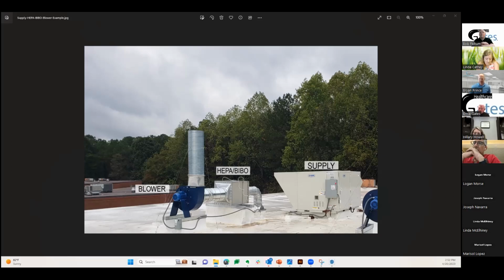Hot gas bypass solenoid valve is only a band-aid, and the point of having a hot gas bypass is to keep the coils from freezing up. That tells me right off the bat that you designed the wrong system and you're trying to put a band-aid on it, which may be okay. But in the beginning, if this is a brand new project, I beg you to do a modulating or dual compressor system.